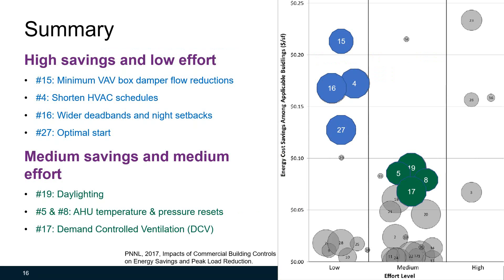Here's the summary of what we discussed today. High savings and low effort advanced control strategies include Number 15, minimum VAV box damper flow reductions; Number 4, shortened HVAC schedules; Number 16, wider dead bands and night setbacks; and Number 27, optimal start. Medium savings and medium effort measures include daylighting, Numbers 5 and 8 AHU temperature and pressure resets, and Number 17 demand controlled ventilation. Advanced rooftop unit controls is a high-cost measure with significant impact, but only applicable to small and medium commercial buildings without a building automation system. Cooling tower VFD controls is also a high-cost measure, only applicable to large commercial buildings with a cooling tower.